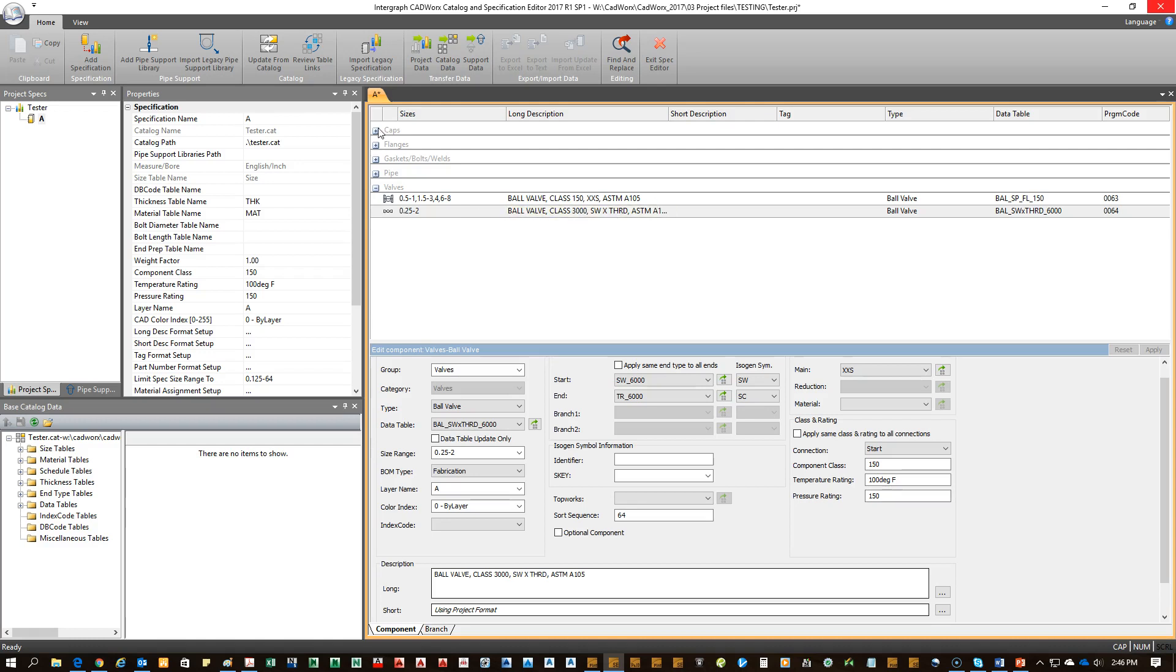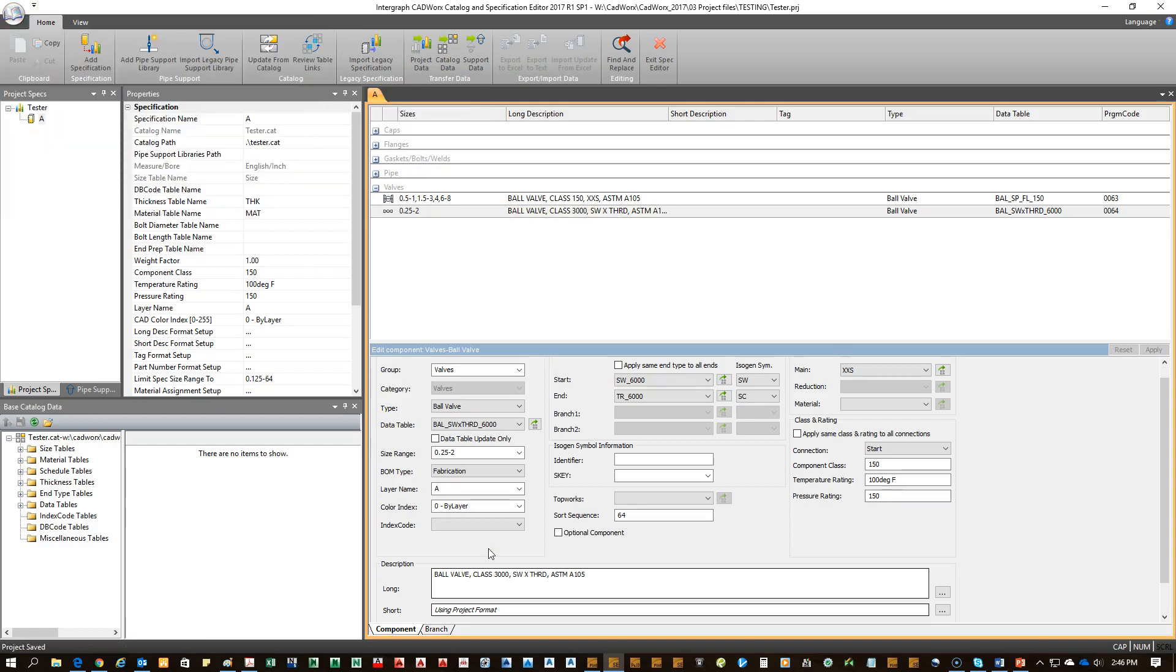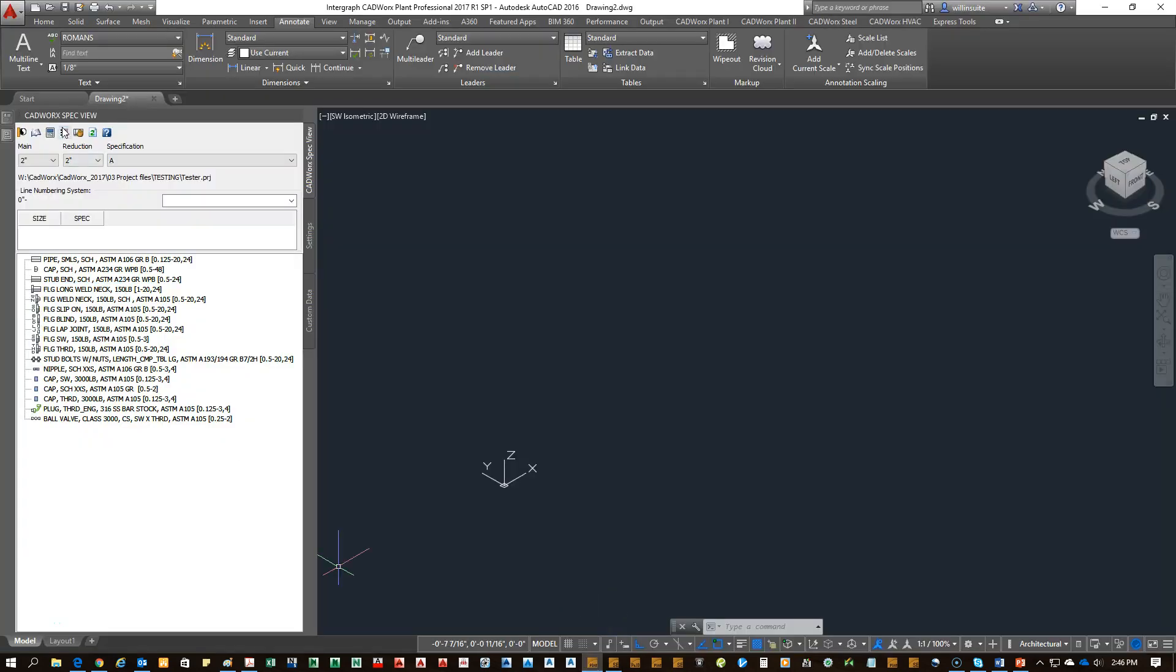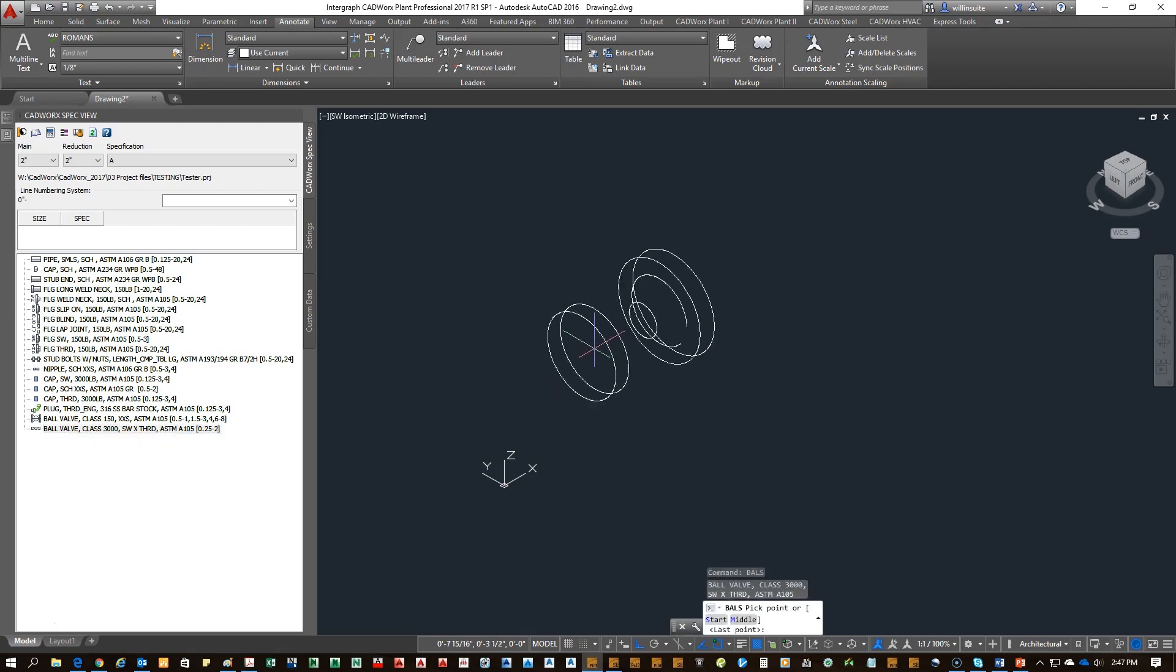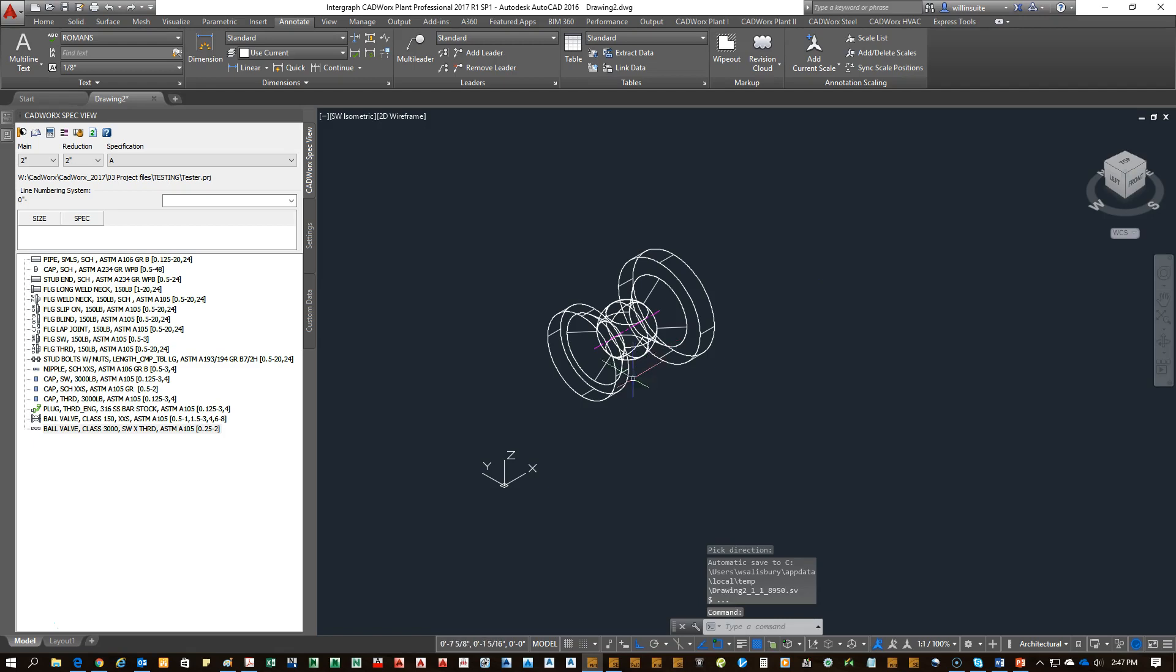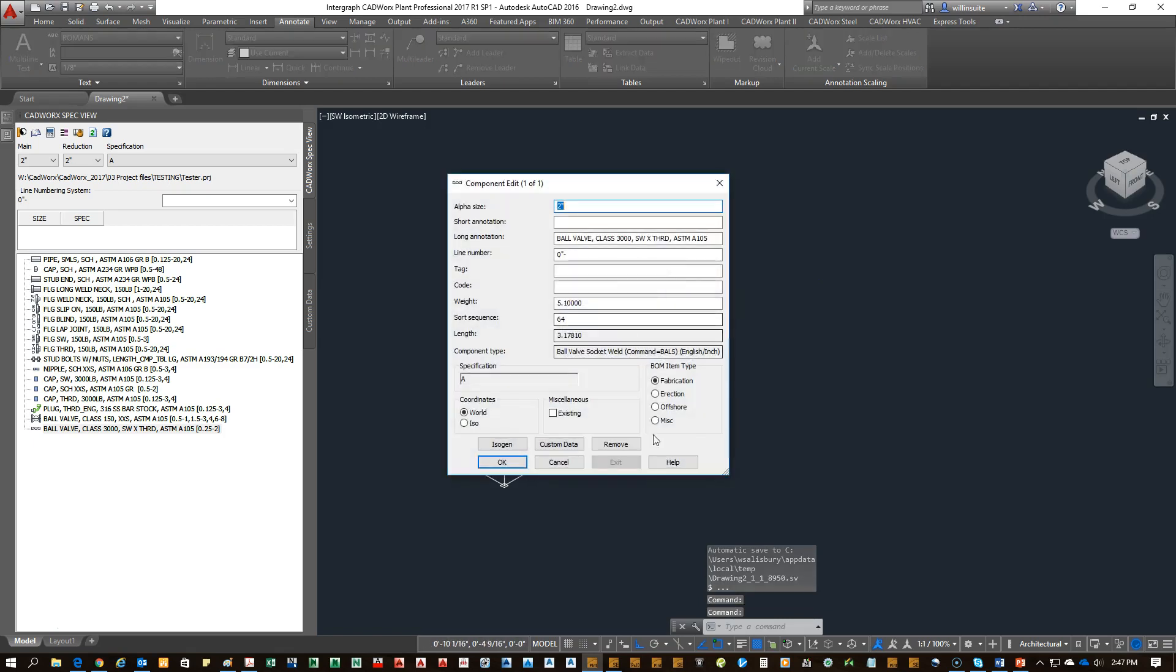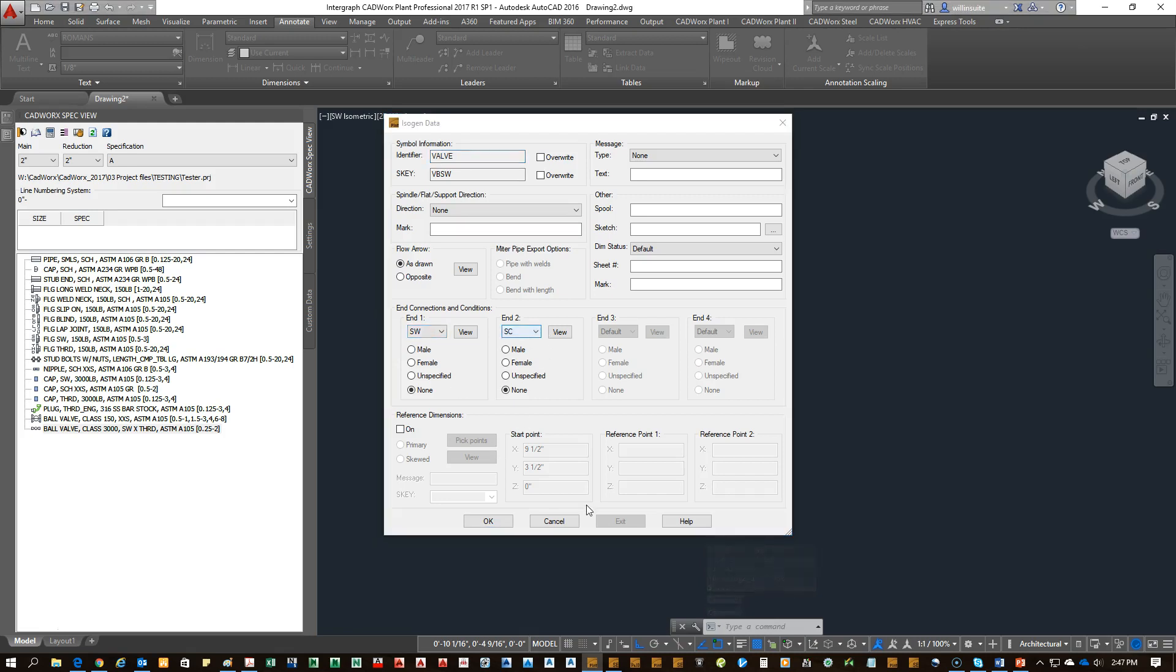Now we have our component in our spec. Go ahead and save. Save. Then open up a plant session. If you already have it open, reload your spec. You should see ball valve socket weld by threaded. And if you double click that, it should show in the isometrics, one side socket weld and one side is screwed, which is threaded. You have now completed making a valve of special end types. Thank you.